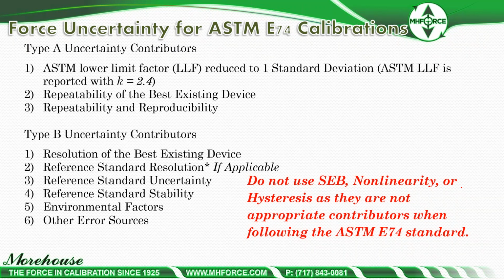Looking at uncertainty, here's what we want to consider. The ASTM lower limit factors: the type A, by statistical analysis, repeatability of the best existing device, repeatability and reproducibility, and then we have type B, resolution of the best existing device. Going to need to do some type of test. We need reference standard resolution. If dead weights, we're not going to have resolution. Reference standard uncertainty. Stability is huge. A lot of people forget to put stability.